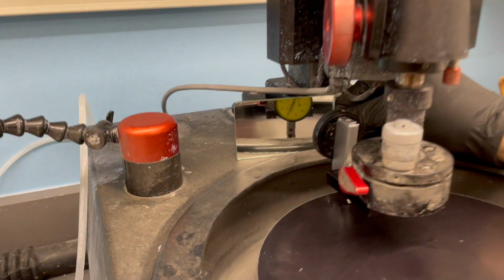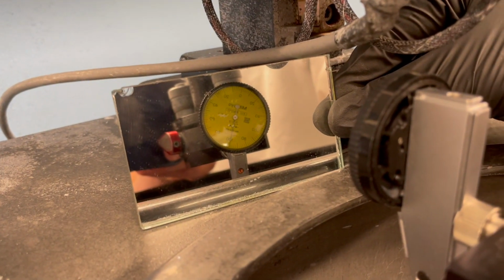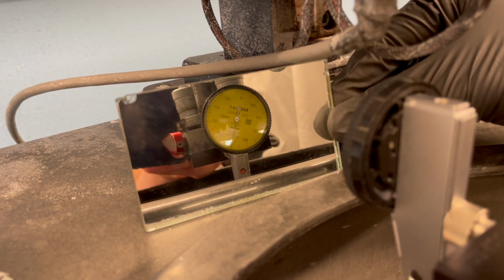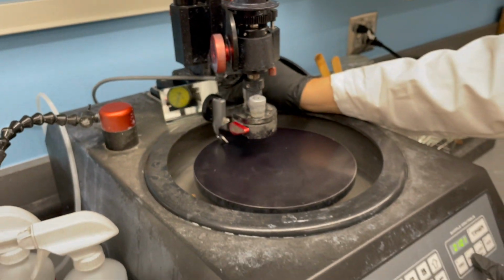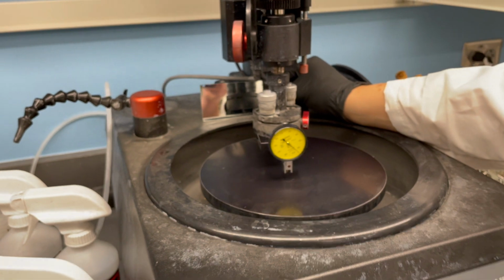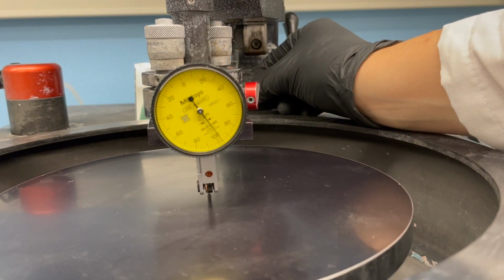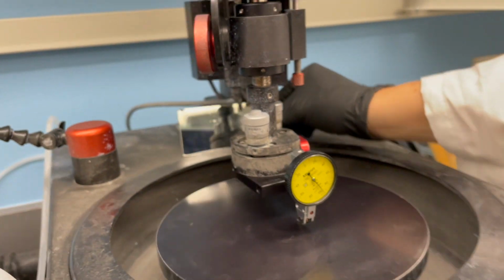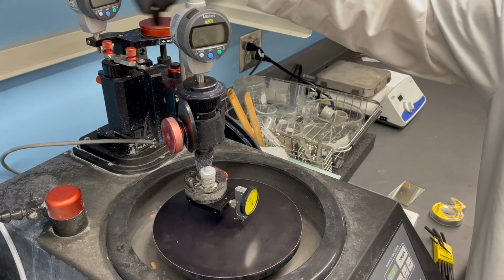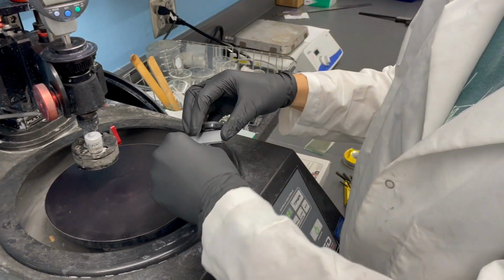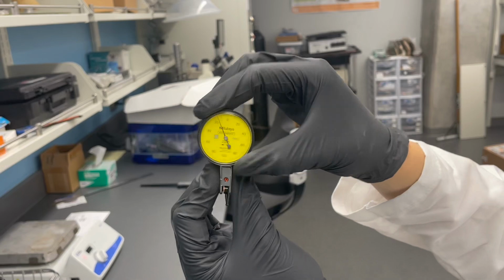Rotate the dial to the 12 o'clock position and use the mirror to confirm the dial reads 100. Raise and lower the arm to adjust. Then rotate the dial to the 6 o'clock position and use the Allen wrench to adjust the front center bolt until the dial returns to 100. Repeat until no further adjustments are needed. Remove the calibration tool and take off the dial. Rotate the dial so that the needle points to 100.